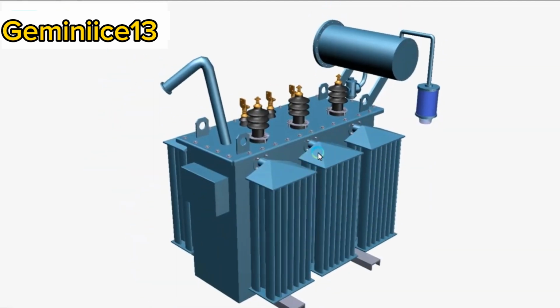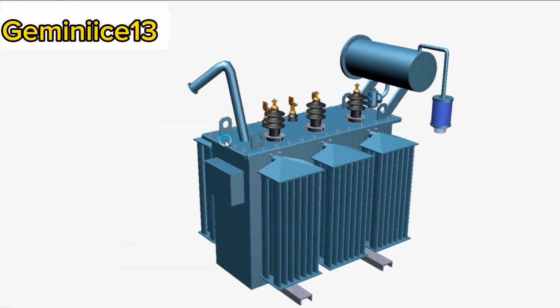If there is any problem and the relay cannot sense it in time, the oil rushes out of the vent. The explosion vent acts as an emergency exit for oil and gases inside the transformer. It is a metallic pipe with a diaphragm at one end.